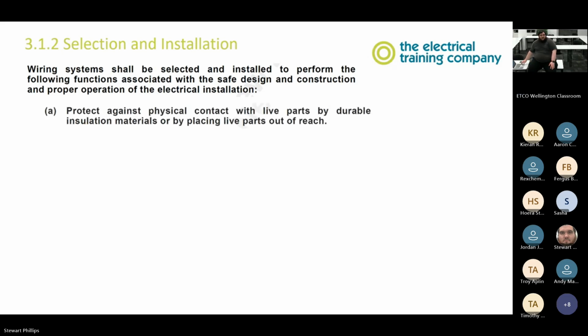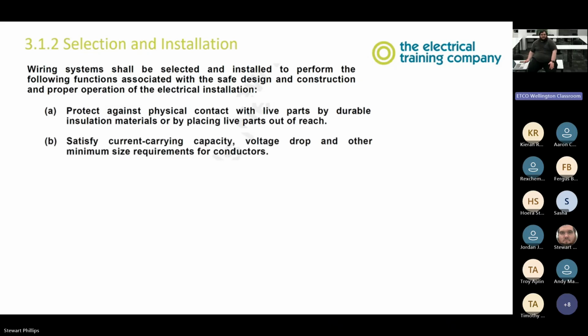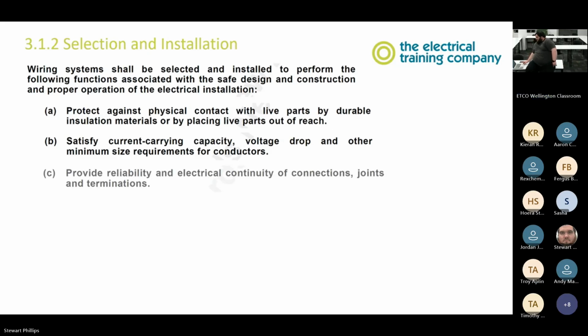Am I wrong there? Cool. So protect against physical contact with live parts by durable insulation materials or by placing live parts out of reach. Cool. Satisfy current carrying capacity, so that's cable size, volt drop, and other minimum size requirements. We must provide reliability and electrical continuity of connections. So we need to make sure our joints and terminations are going to stand up to the test of time and be reliable. So no twist and tape and no use of solder. Why do we not use solder anymore in general electrical work?